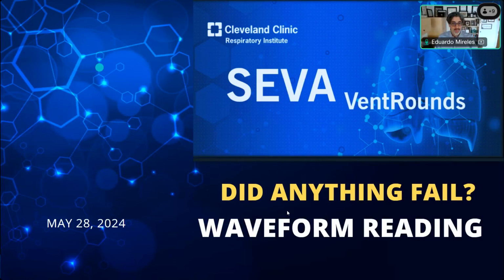What are you thinking here, Roberto? I'm thinking I've got to read the manual and figure it out, because everything you said is correct. There was once upon a time an infant ventilator that was in pressure control, would cycle if the tidal volume reached a preset threshold, but that's extinct now. I don't think any ventilator does that anymore. So this is odd. It doesn't fit the pattern. So it could be something else that occurs here, and it's not cycling the way it should be, and it's going to another backup mechanism. I don't know. It's a challenge. I'll figure it out.